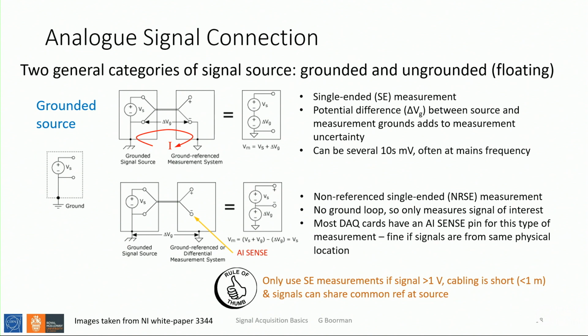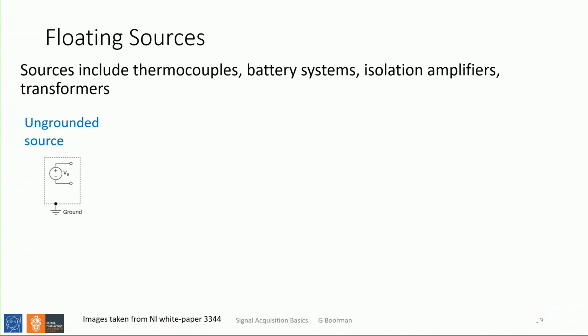The rule of thumb for single-ended measurements on the ADC: make sure your signal is big, greater than a volt, and your cabling is short. Short cabling implies that your signal source and signal sinks are adjacent, and that they can share some common reference, some common ground. Then there are floating sources, things like thermocouples, battery-based systems, and so on. It's an ungrounded source. Your equipment is probably earthed, but your output signal is not referenced to that earth. It has its own floating output.